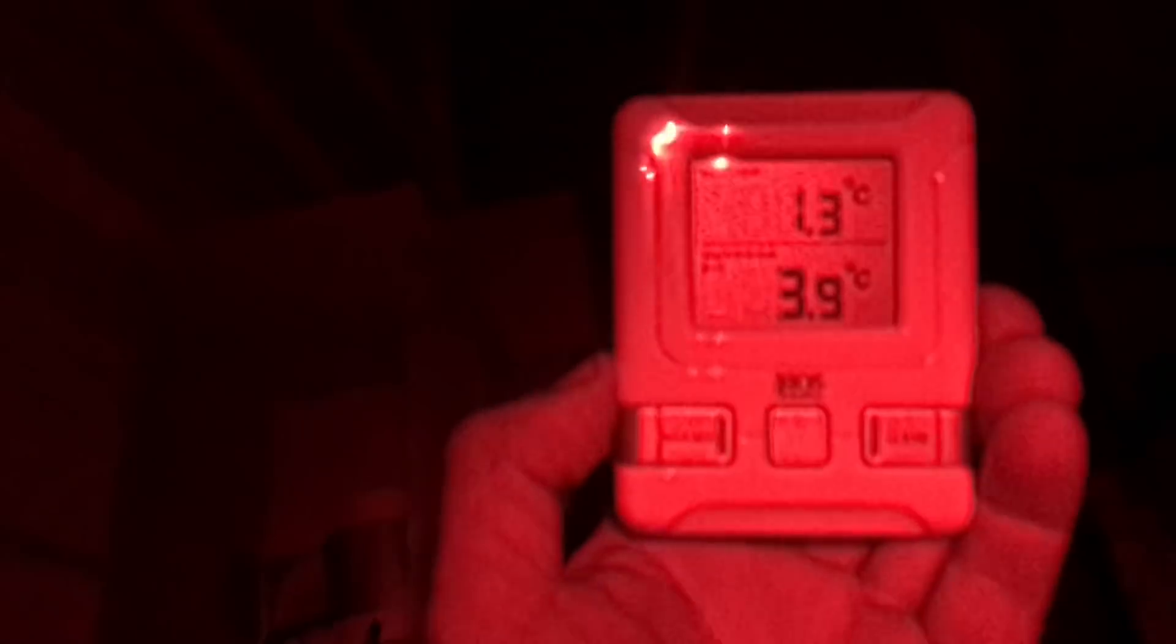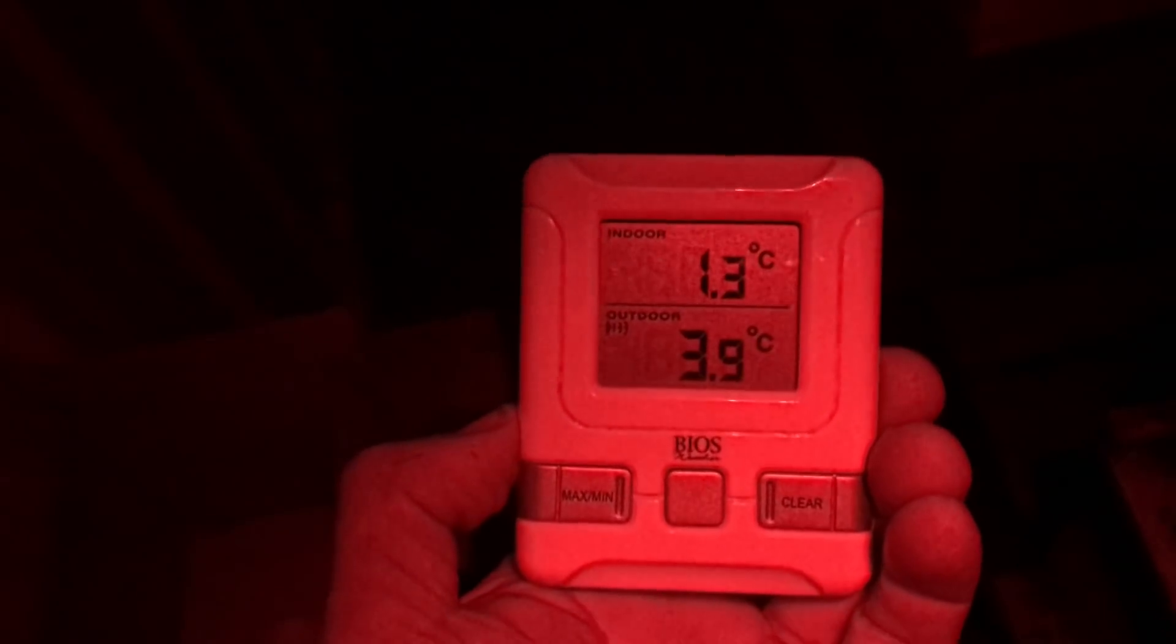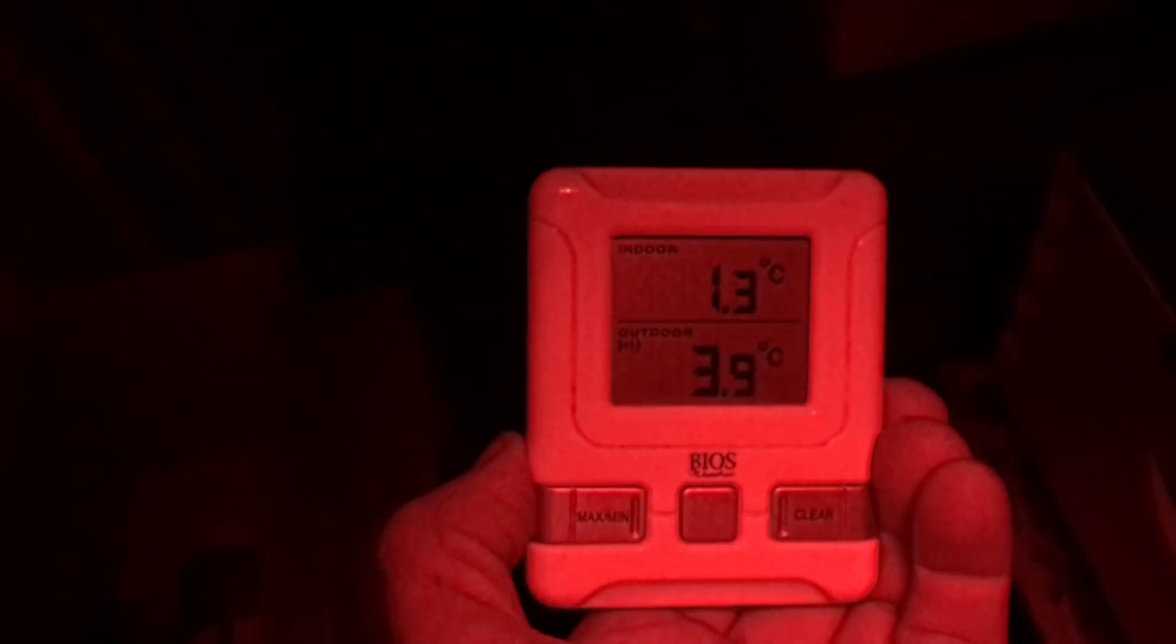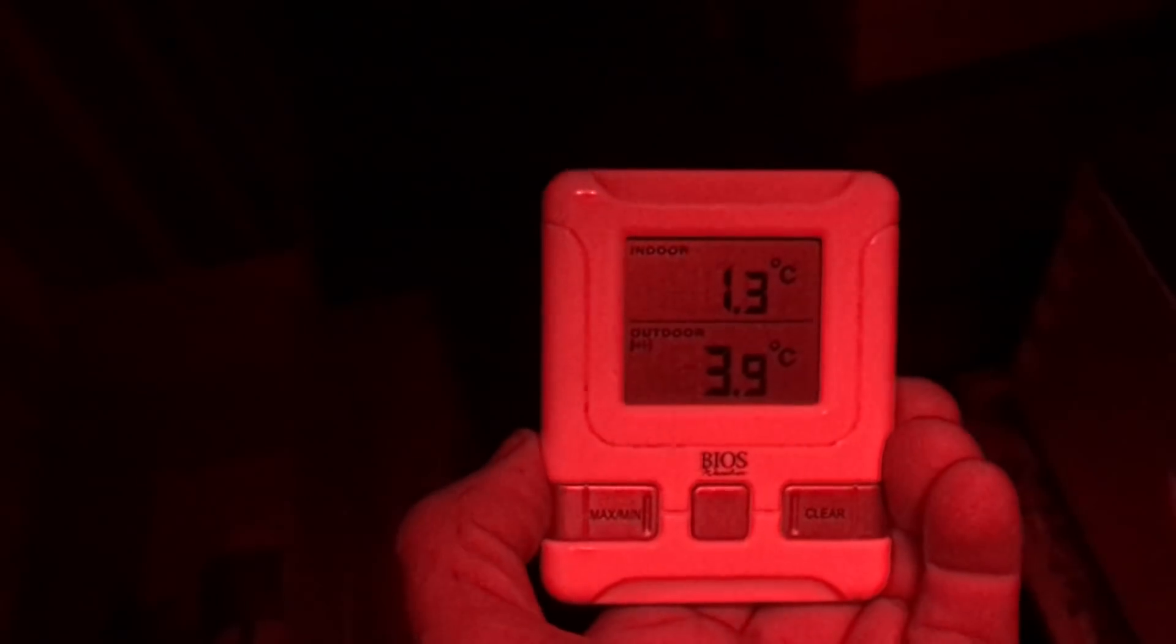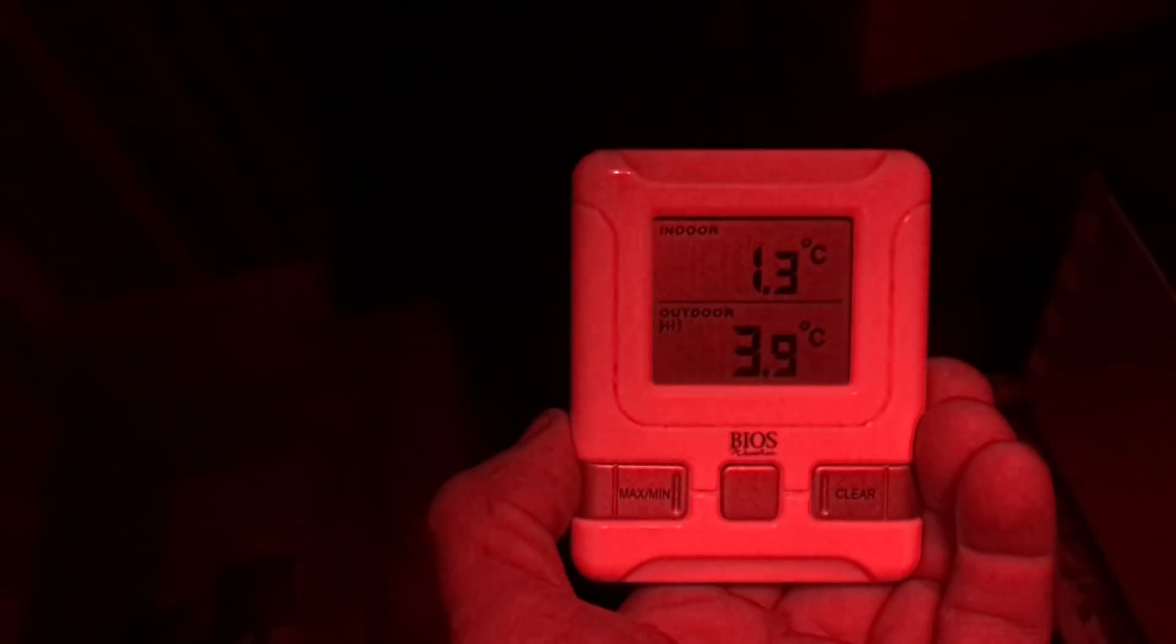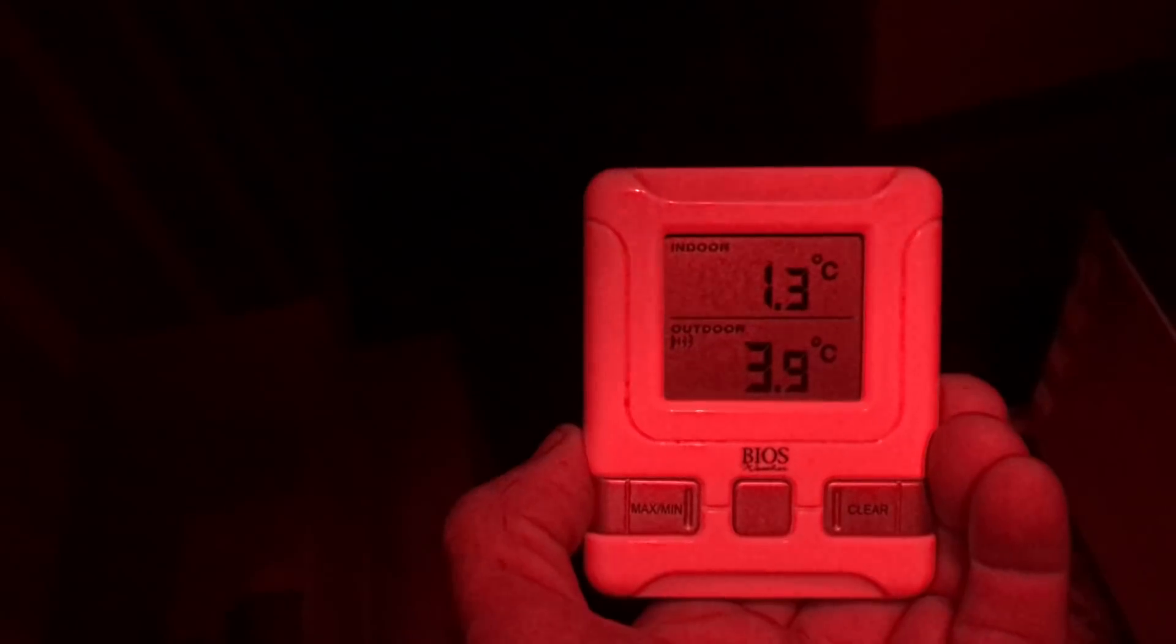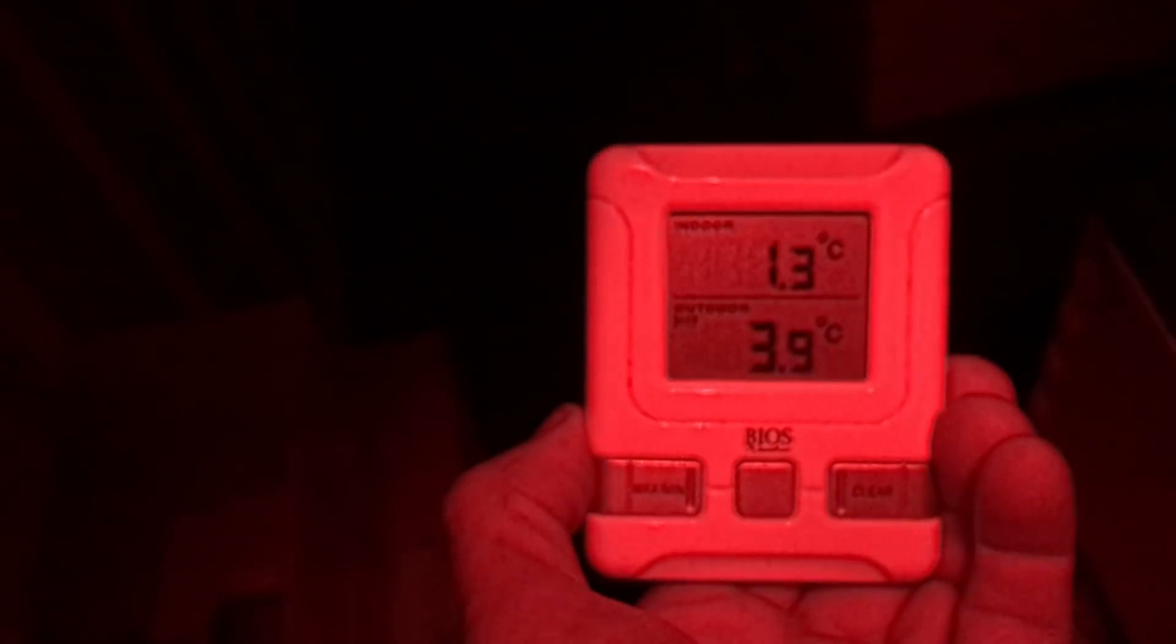So the fans are at idle. My high-tech temperature gauge, so about one degree around the outside of the shed and right in the middle of the bees is almost four. So that's quite content. That's showing the cold air that's coming in and it's taking a little bit to take that cold air and mix that cold air with the warm air within the shed. And there's very little air exchange out, so that extreme cold air coming in is taking a little while to mix. That's what that's telling me.